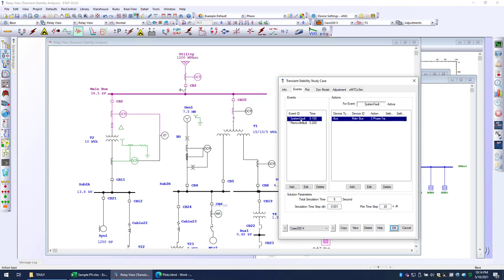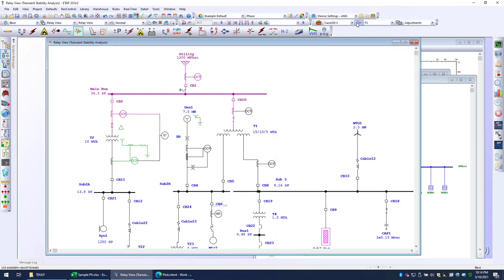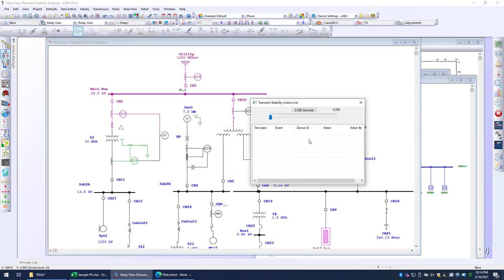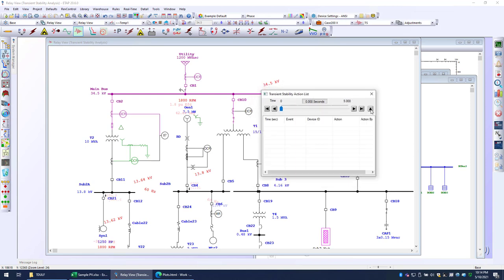So here is the system fault at 100 milliseconds on my main bus location, which is just to the left here, and then 200 milliseconds later, it's going to clear, and I want to see what the system frequency is going to be for that. So I'll go ahead and run my transient stability. I will look at the events right here. So I'm going to step through the actions.